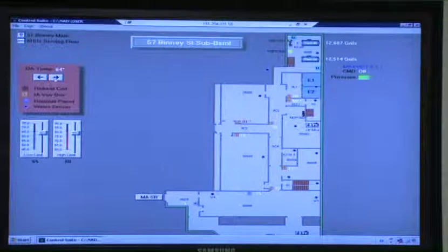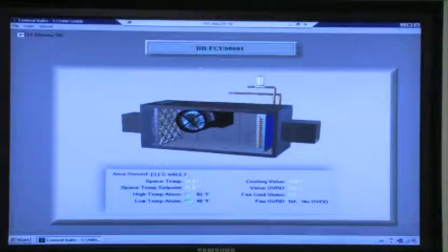Okay. Alrighty. There's a fan coil unit down there, 00211, right? It's supposed to go in there, over near the connection. Down the right bottom here? Isn't there one in that area? There's a T-stat right there. It's a big unit. Fan coil. Yeah. We have the valves overridden open on the sub-basement stuff for the balance, so it finishes balancing, so if you see stuff overridden.